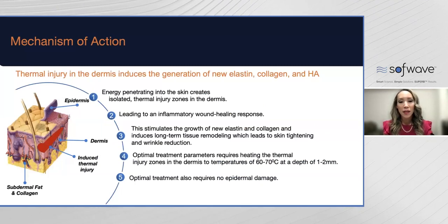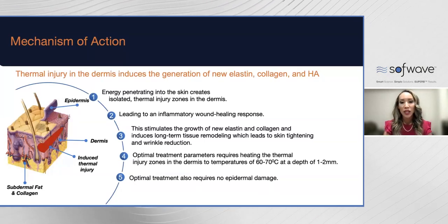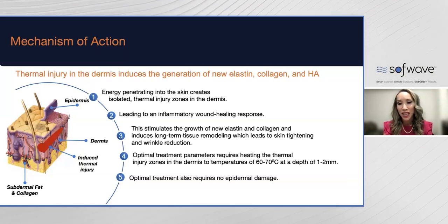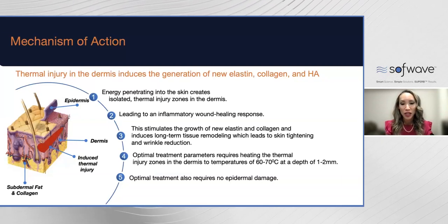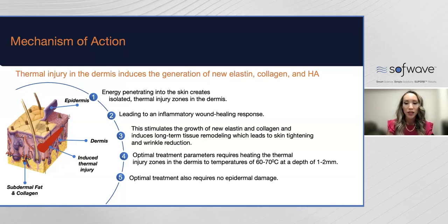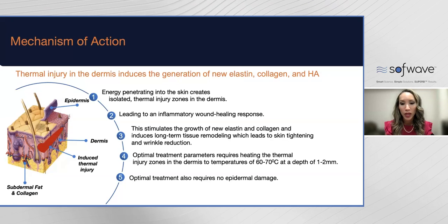So as Brian talked about, we'll just go a little bit into this. What it does is deliver thermal injury to the dermis, which induces generation of new collagen, elastin, and actually hyaluronic acid as well. And so that energy penetrating into the skin creates isolated zones of injury in the dermis, leading to an inflammatory wound healing response. This stimulates growth of new elastin and collagen and induces long-term tissue remodeling, which leads to skin tightening and wrinkle reduction. Now, we know the optimal treatment parameters require heating the thermal injury zones in the dermis to a temperature of 60 to 70 degrees Celsius at that fixed depth of 1 to 2 millimeters. The Sofwave device delivers those thermal zones of injury at that fixed depth of 1.5 millimeters.